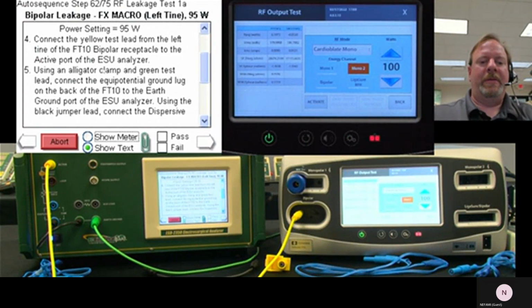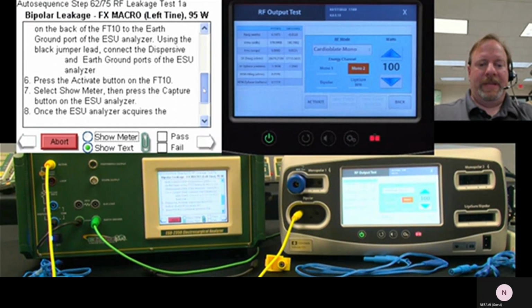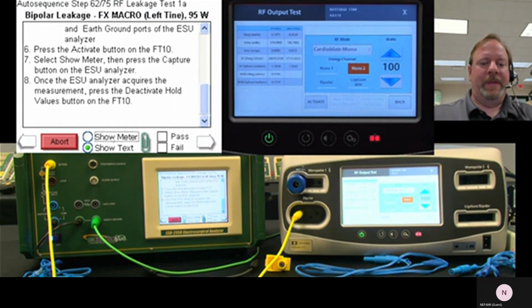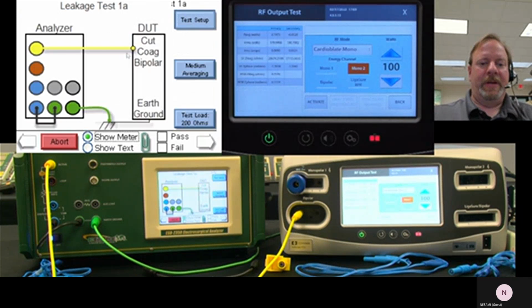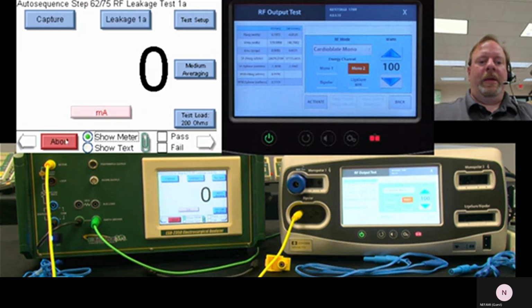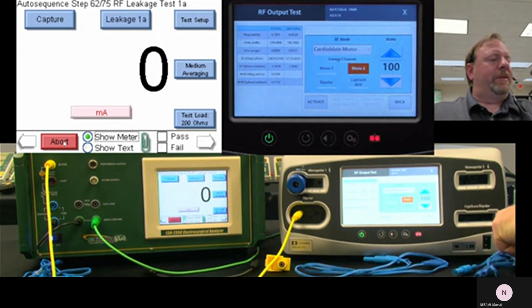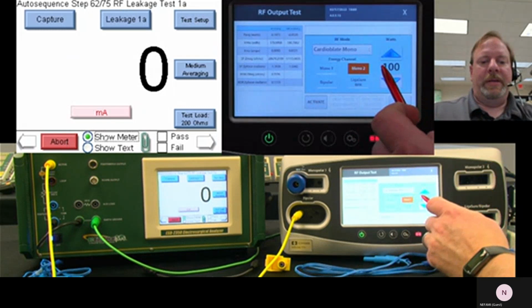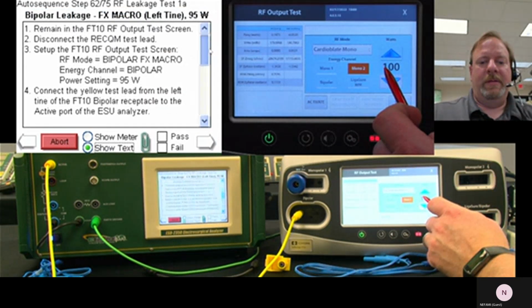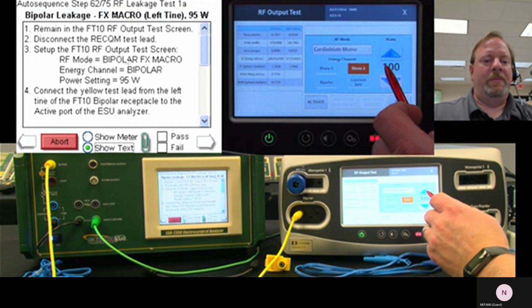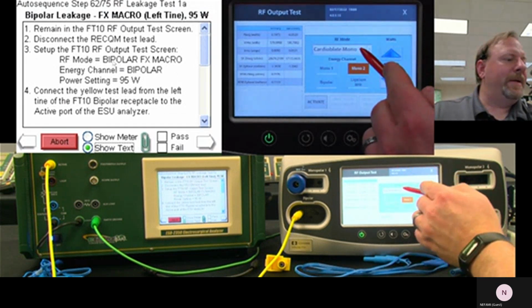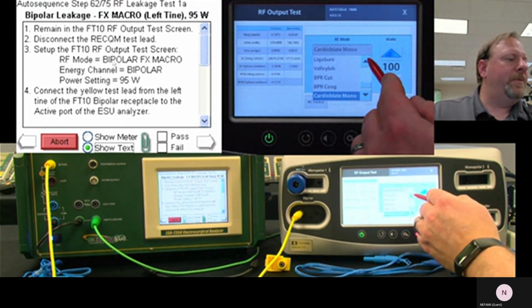Okay, using an alligator clamp. Same ground connection as before. We can go back into our show meter. Yep, cut coag bipolar. We're doing bipolar now. And we can activate the generator, cardioblate. Double check one last time. Nope, we want bipolar FX macro.